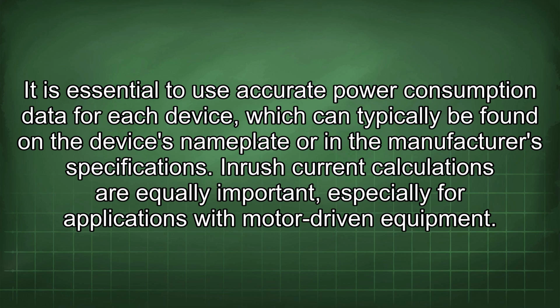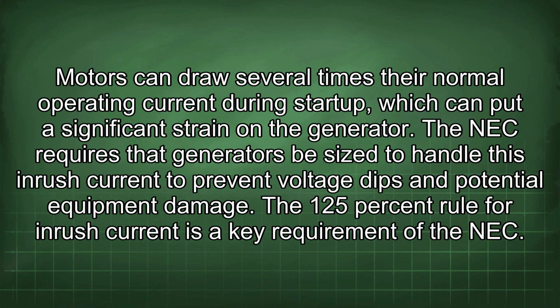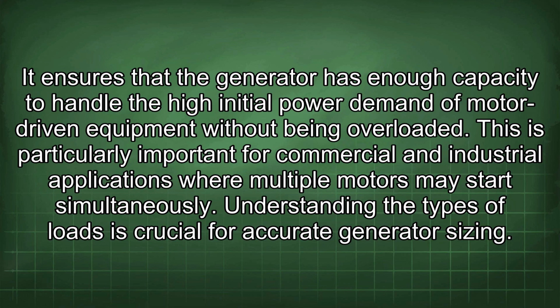Inrush current calculations are equally important, especially for applications with motor-driven equipment. Motors can draw several times their normal operating current during startup, which can put a significant strain on the generator. The NEC requires that generators be sized to handle this inrush current to prevent voltage dips and potential equipment damage. The 125% rule for inrush current is a key requirement of the NEC. It ensures that the generator has enough capacity to handle the high initial power demand of motor-driven equipment without being overloaded. This is particularly important for commercial and industrial applications where multiple motors may start simultaneously.